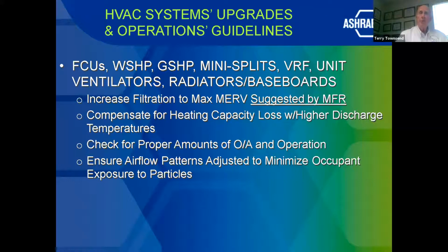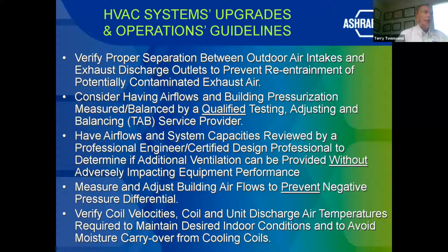Fan coil units, water source heat pump, ground source heat pump: increase filtration again to whatever the manufacturer says is allowed. Compensate for heating capacity loss with higher discharge temperatures, check for proper amounts of outside air and operation, and ensure airflow patterns adjust to minimize occupant exposure to particles. So now we look at the HVAC system upgrades and operation guidelines. Verify again, this is code requirements, that there's proper separation between outdoor air intake and exhaust discharge. You want to make sure that the building is slightly pressurized, and have it verified by a qualified TAB (testing, adjusting, and balancing) service provider.